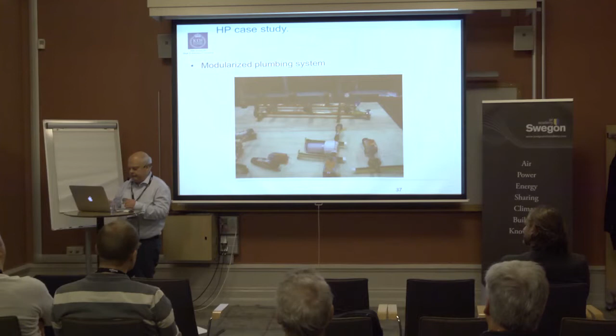I'm moving on to another kind of cooling system. We've been testing this as well at KTH - we didn't end up purchasing it, not because it was bad, but this is mineral oil cooling. You have a bathtub where you sink down your computers, submerged in the fluid, with a special box that pumps the oil around in the bathtub and also has a built-in heat exchanger, so you can water cool that.